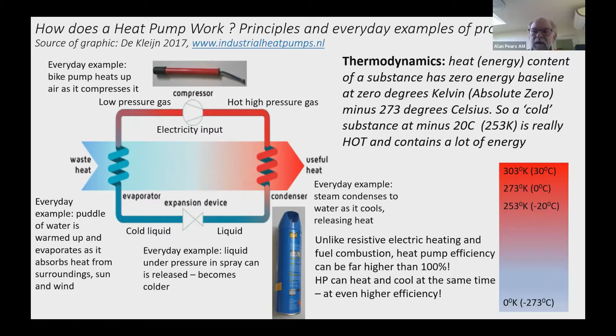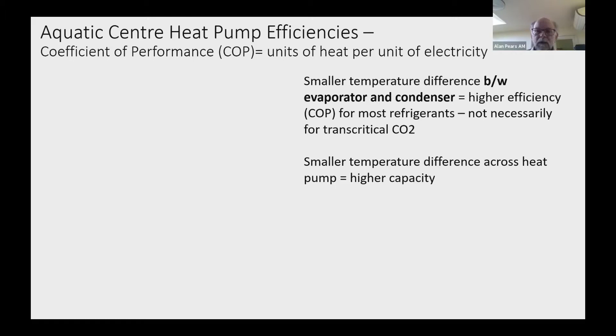Now, one of the things that I hear debated a lot when people are looking at aquatic centres is this issue of how efficient is the heat pump. And this is where the term coefficient of performance comes in. So instead of saying a heat pump is 500% efficient, we say it has a coefficient of performance of 5. That is, we're getting 5 units of heat for each unit of electricity. So that's the key element there. And I'll just show you this now. Sorry, graphs that are.